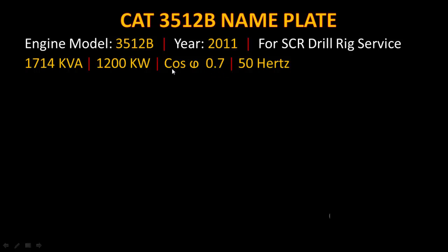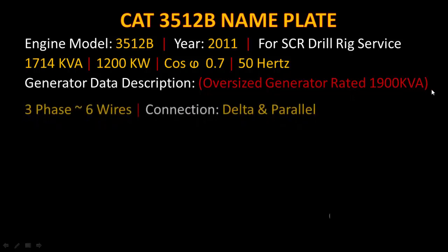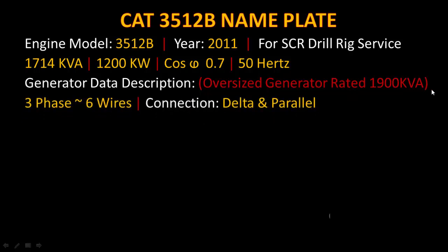Now we see its power factor, real power, and apparent power. Its power factor is 0.7, represented by cos phi. Its real power is 1200 kilowatts and its apparent power is 1714 kVA. The generator frequency is 50 Hz.